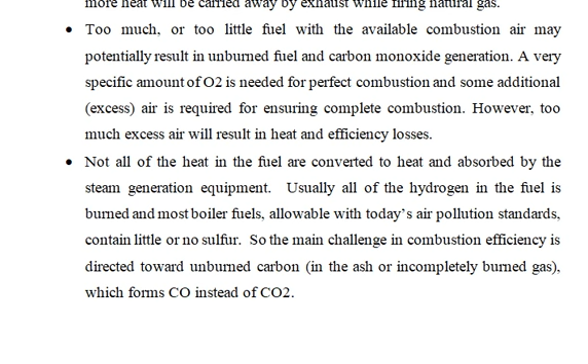The main thing. Then the last point: not all of the heat in the fuel is converted into heat absorbed by the steam generation equipment. Usually all of the hydrogen in the fuel is burned, and most boiler fuel allowable with today's air pollution standards contains little or no sulfur. So the main challenge in combustion efficiency is directed toward the unburned carbon in ash or incompletely burned gases which form CO instead of CO2.